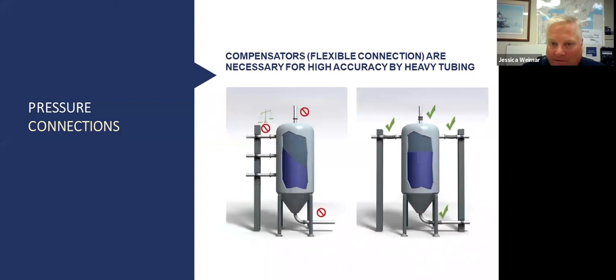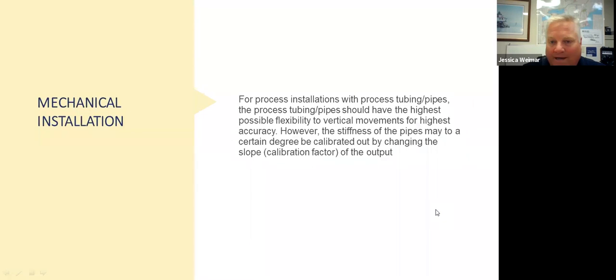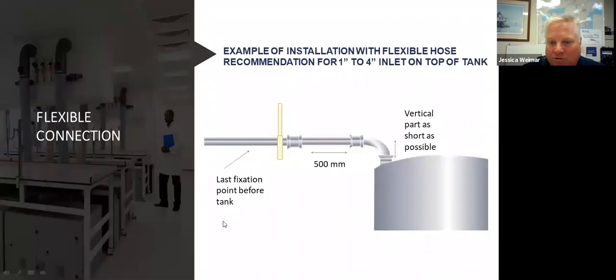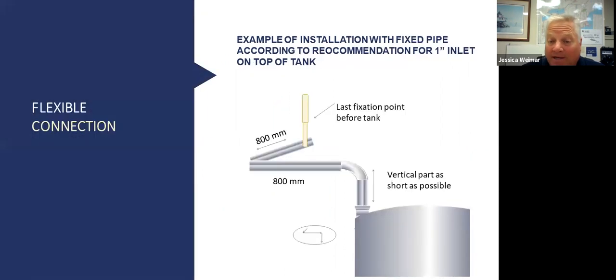Okay. One of the other things we think about in installation, and again, we can go further into depth in the next presentation, is how we connect our load to the process lines. One of the things that is true of anybody's load cell system, whether it's mine or anyone else's, is that the load needs to be able to move. If you bind the load up and it can't move, then you can't measure it. So you've got to think about rigid piping. That's a no-no. You need flex joints. You've got to think about ways to allow the tank to move. Where's the last place I'm going to support the piping? How far away from the tank so that the tank doesn't bind? Those are important things that we can help you with.